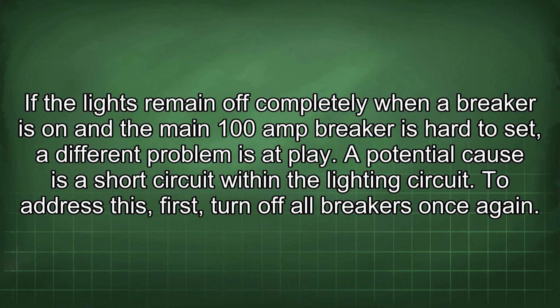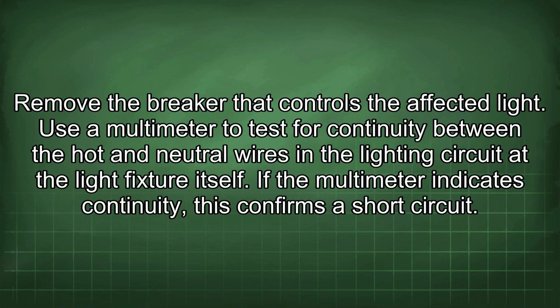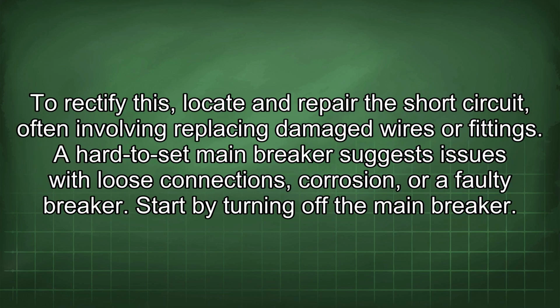to set, a different problem is at play. A potential cause is a short circuit within the lighting circuit. To address this, first turn off all breakers once again. Remove the breaker that controls the affected light. Use a multimeter to test for continuity between the hot and neutral wires in the lighting circuit at the light fixture itself. If the multimeter indicates continuity, this confirms a short circuit. To rectify this, locate and repair the short circuit, often involving replacing damaged wires or fittings.